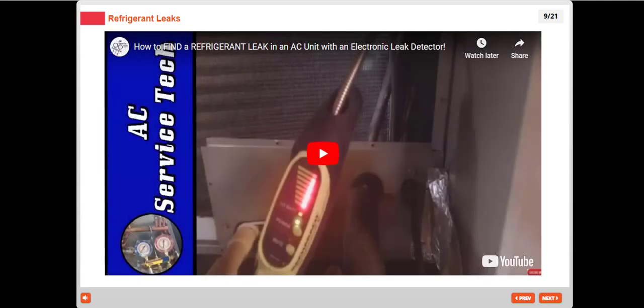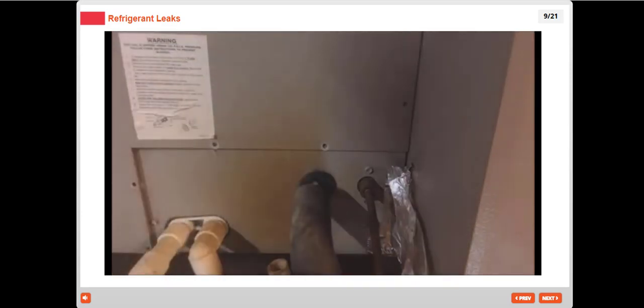So right now we're looking at the indoor evaporator coil, and we're going to go ahead and open up the cover. We're going to use the Bacharach Informant 2 leak detector, and we're also going to use a bubble leak detector as well. We've had our Bacharach Informant 2 powered up for at least 30 seconds, so we're going to go ahead and sniff around.